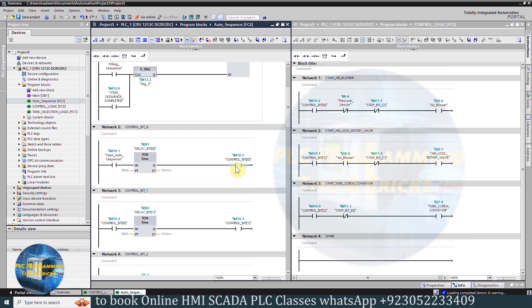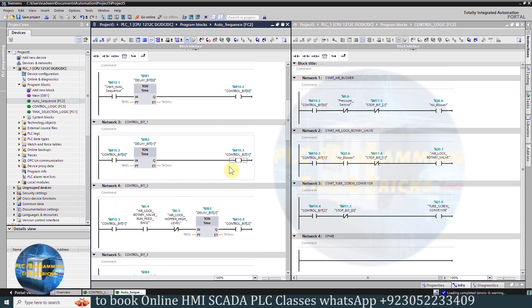In Network 3, as control bit 0 turns on, it will start another 5-second timer. After this timer is over, it will turn on control bit 1. In Network 2 of the control logic function, as control bit 1 turns on and the air blower is running, it will turn on the airlock rotary valve Q0.7.